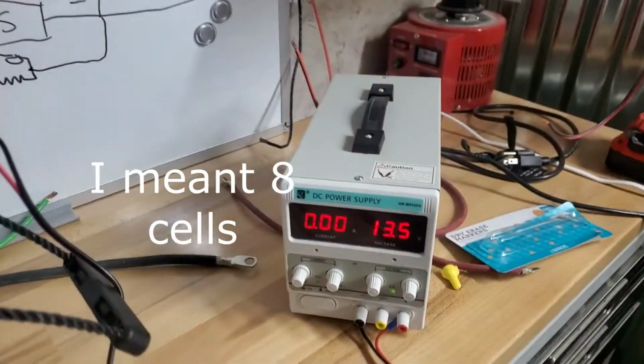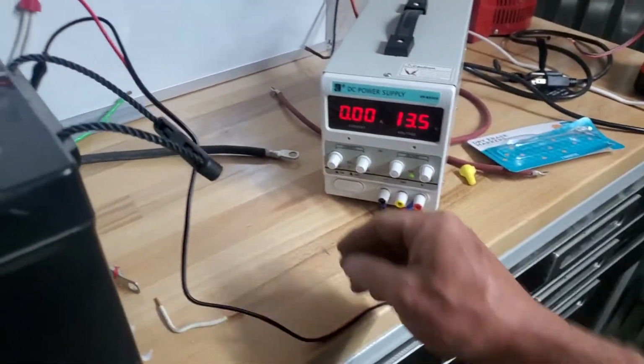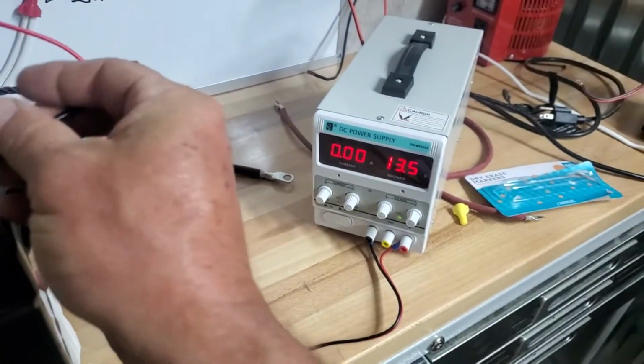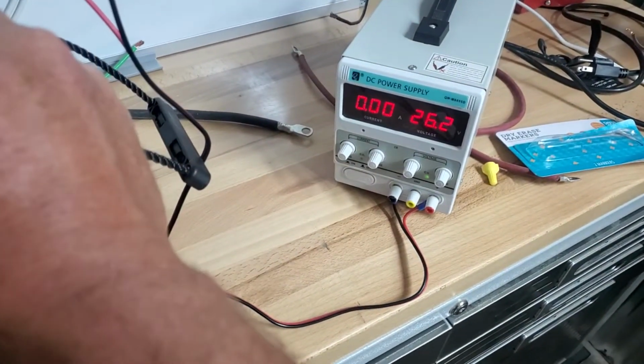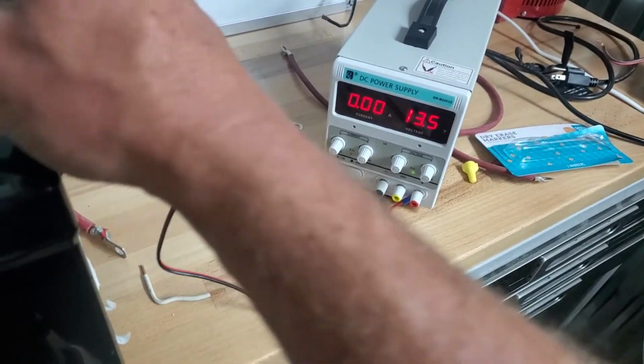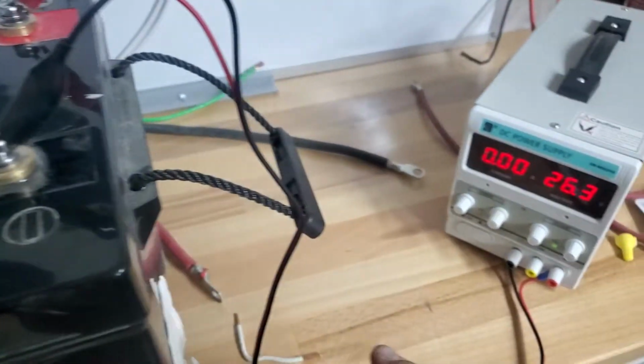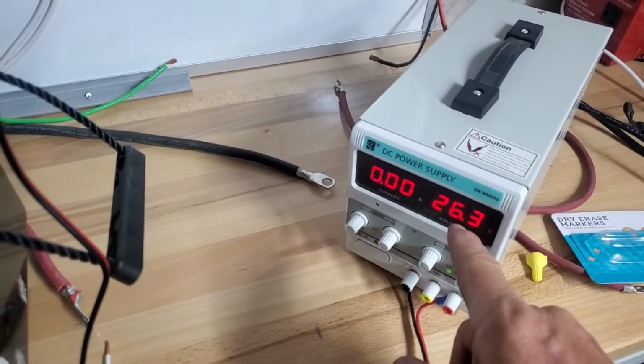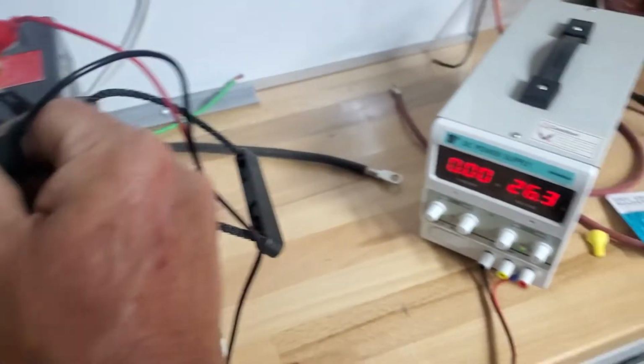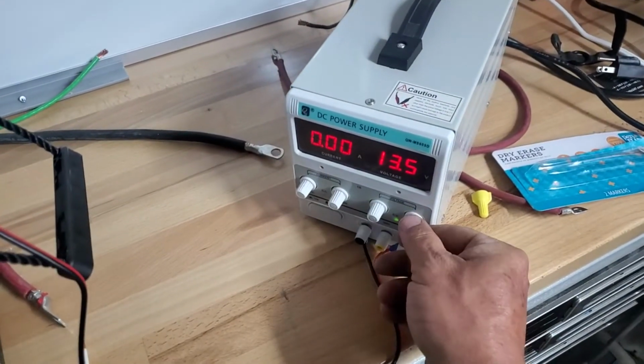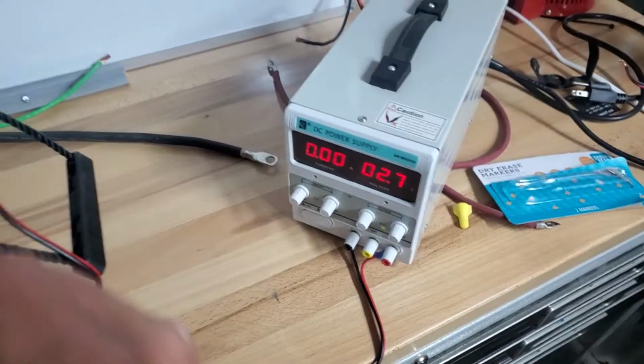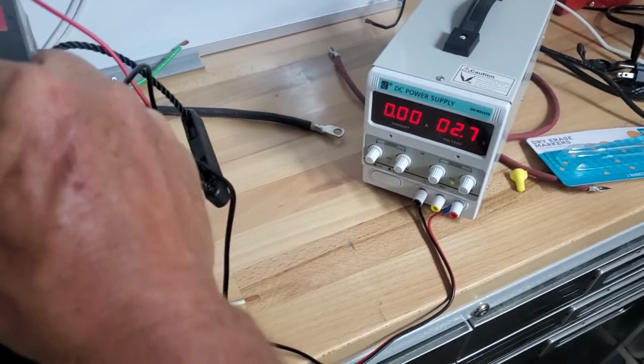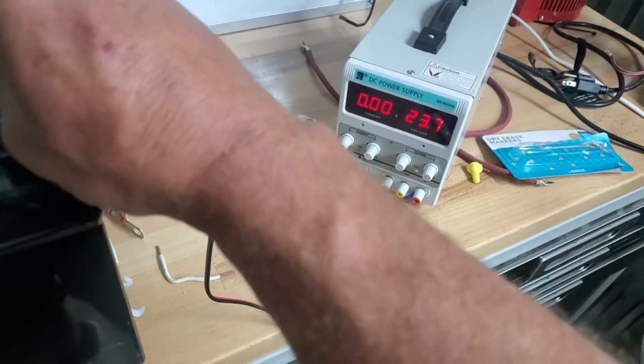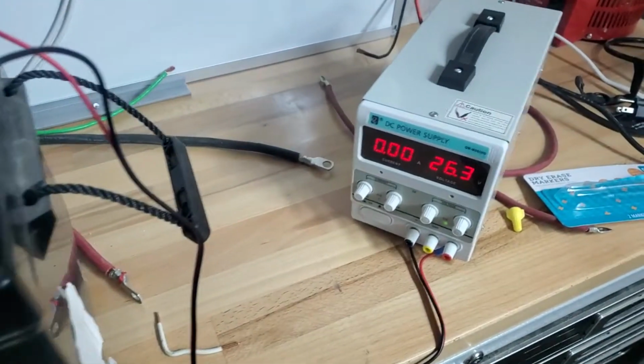Since this is a 24 volt unit with 8 cells, I'm going to connect a bench power supply to it, set at 13 volts. As I connect it up, the voltage from the battery should feed back to this power supply meter and push it up to 26 volts. As I pull it off, you can see that's what the voltage meter is set at. I can set this at 4 volts, connect it up, and you'll see it jump to 26 volts. Now let me show you some strange behaviors of a BMS.